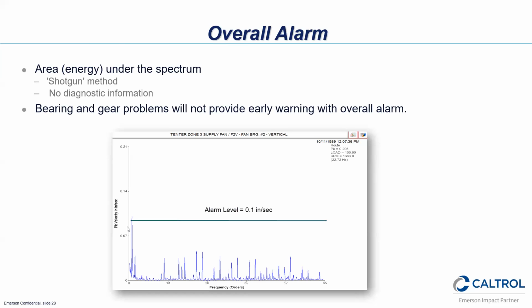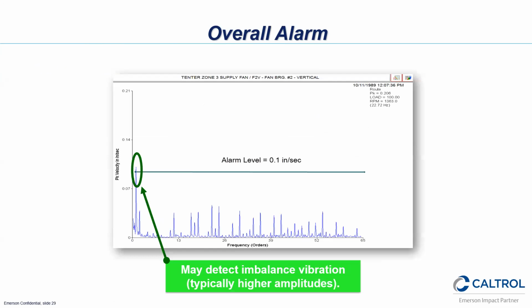Here's another example of an alarm limit, set here at 0.1 inches per second, which is pretty low. But you do have a lot of events going on with bearing frequencies down here in the higher frequency that are not affecting that number. Here's one where there's still more going on. The rotational frequency amplitude is reaching an alarm level here, but it's still low. But that's all you're going to see in an overall alarm level, and you won't see anything that's going on with the bearings.